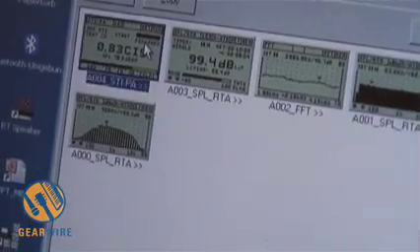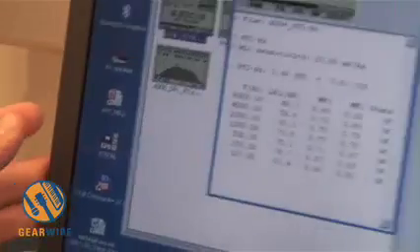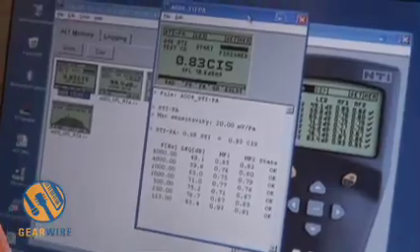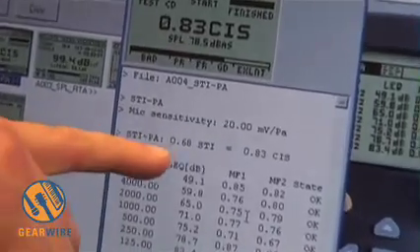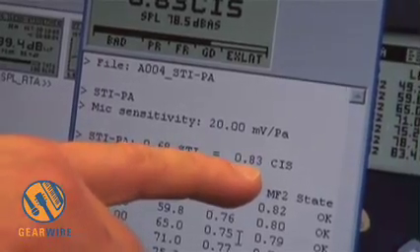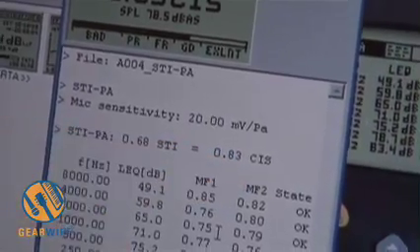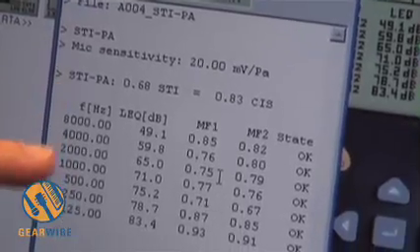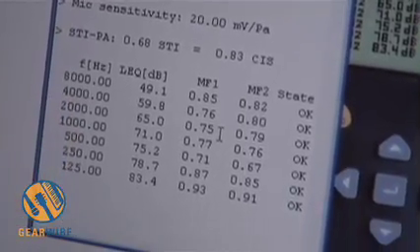We can make a double click on it. So we see now the detailed results. We have an STI value of 0.68 and the common intelligibility value of 0.83. Also all the detailed measurement results for your documentation.